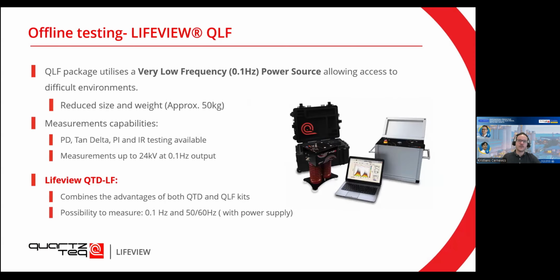On the other hand, we also provide a very interesting solution that we call the very low frequency measurements. At 0.1 hertz, the whole kit already contains a high voltage source. The measurement kit, the laptop, and the high voltage source altogether would be around 50 kilograms, so it would be quite easy to transport to sites. It also has the polarization index and insulation resistance testing available, and you can make measurements up to 24 kV. This is a more portable solution because you don't need the external power source in the plant. You can bring your own.